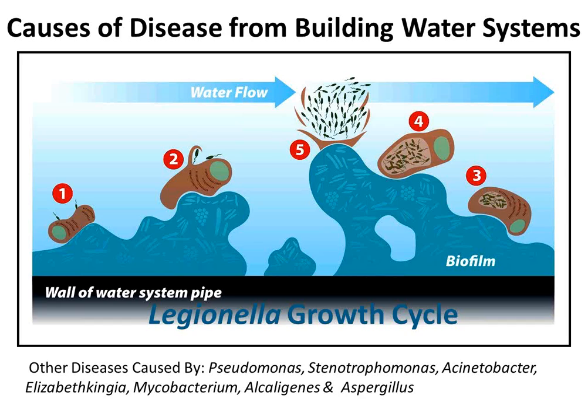Especially if there's no disinfectant or low disinfectant in the water, biofilms develop on the surface of the pipe, and they are comprised of many kinds of microorganisms, and we've symbolized that with all these little circles and rod-shaped structures. Those are bacteria that are growing on the wall of the pipe. Now, other microorganisms feed on those biofilms. They graze on the biofilms, like sheep grazing on the grass, so to speak. That's not a perfect metaphor, but it's close.